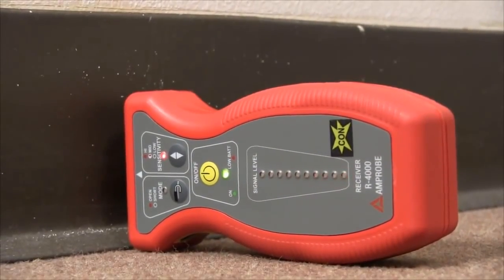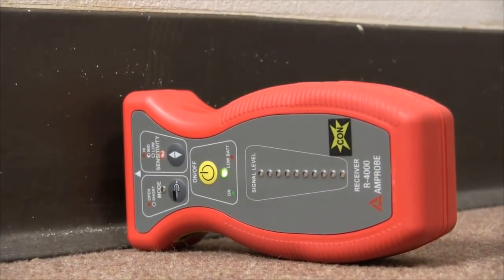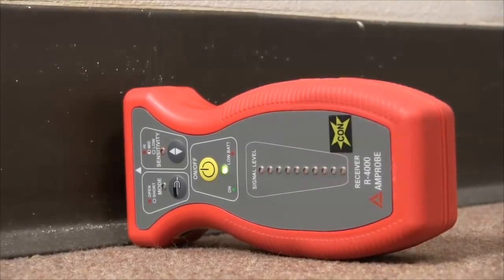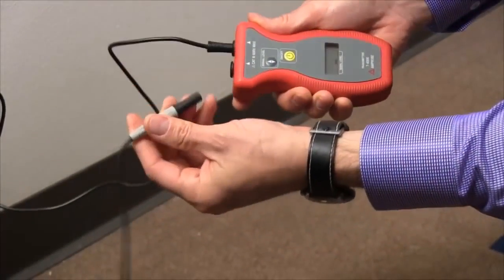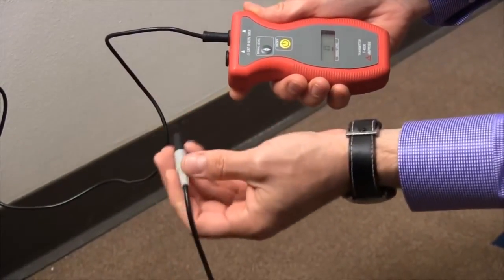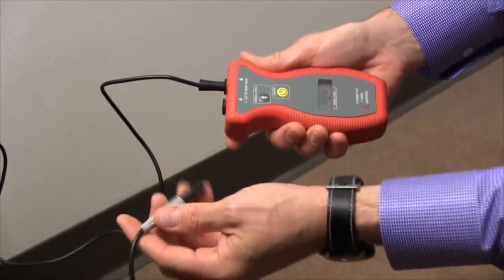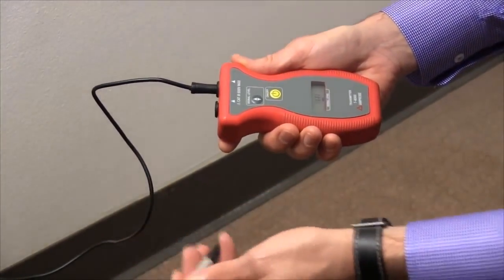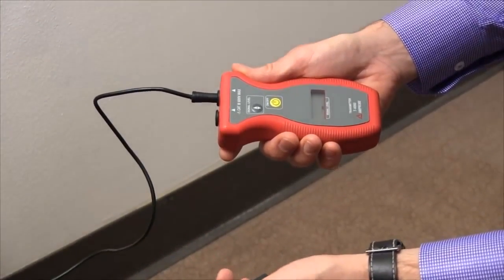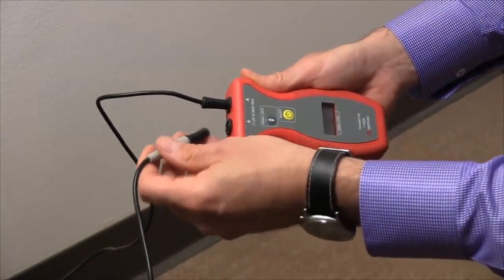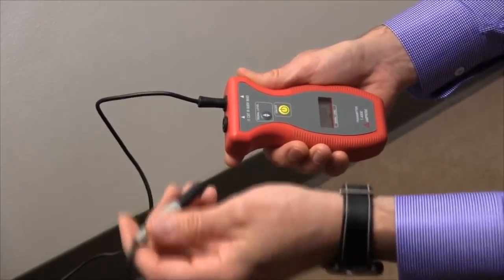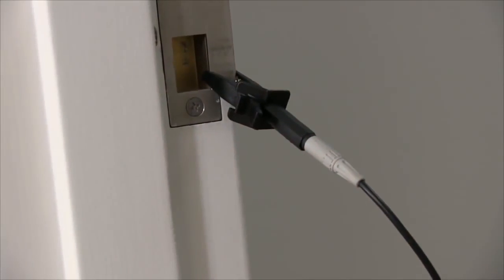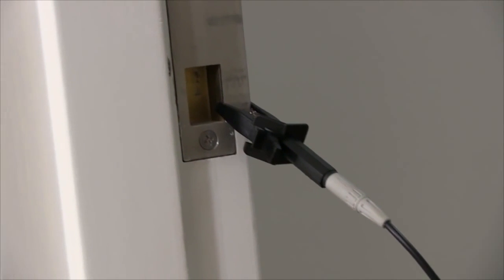Now, I said we would show what happens if you don't have this grounding plug plugged in. The other end of this grounding plug is, in this case, attached to a metal doorframe. It could also go out a window to the ground, or perhaps to a screwdriver plugged into the ground. It's important to have a valid grounding source, such as a metal standpipe or some other metal object.